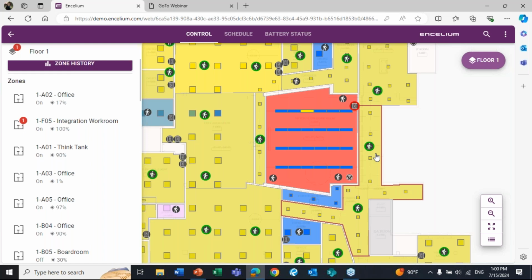Run the time schedule. The time schedule has a higher priority over occupancy sensing, meaning that if there's a time schedule from 12 to 8, basically these occupancy sensors are disabled. They're still tracking information, but they're not actually controlling the lights because the time schedule says, nope, I know what you wanted in your sequence of operations. You wanted the lights to stay on during this period.